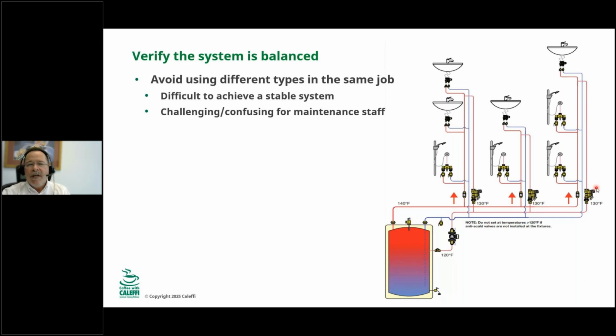Make sure and check each balancing valve. I know that's a lot of labor. The commissioning contractors should do that, but we know that after they're gone, then whoever owns that building really should take ownership and make sure that everything is balanced. And I mentioned before, it's the last, but it's the most important step in commissioning.